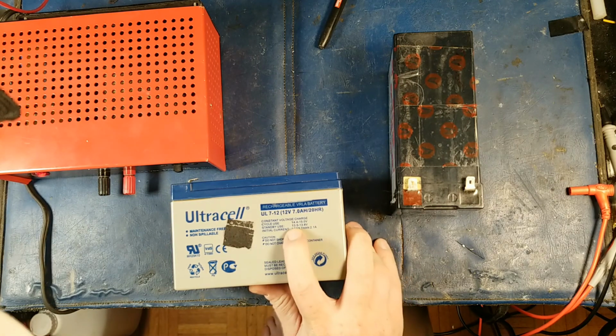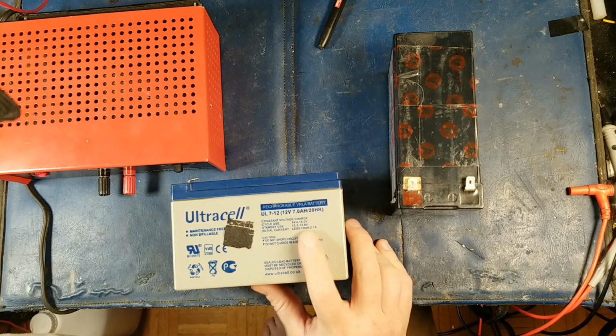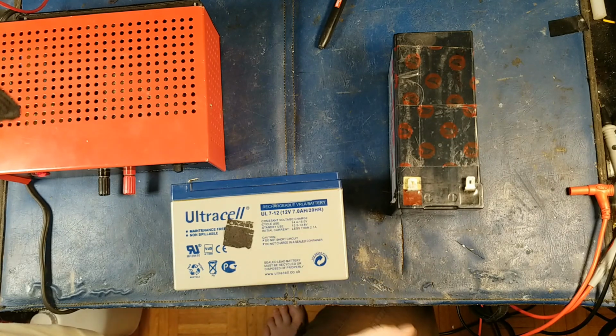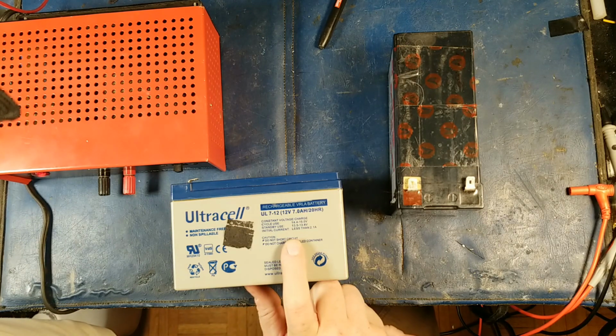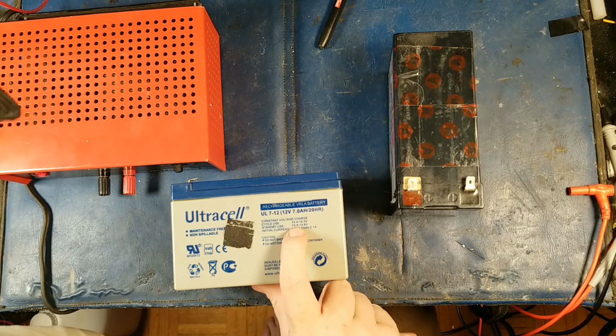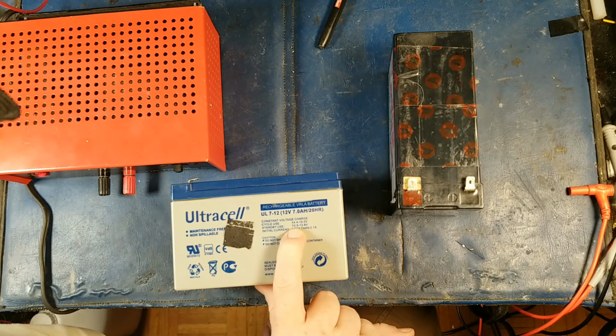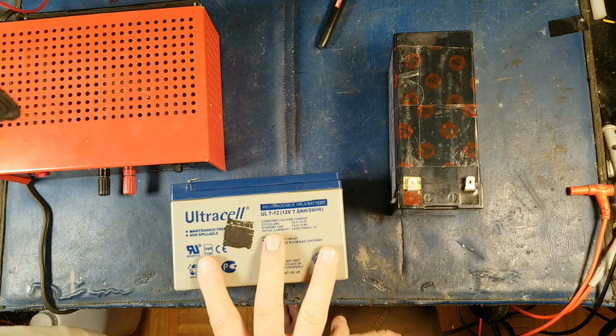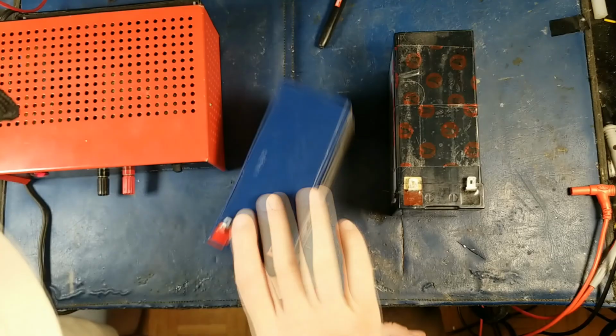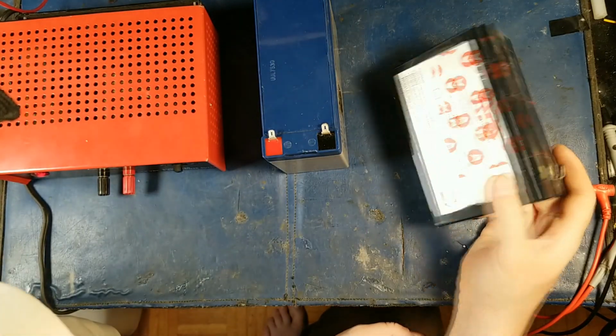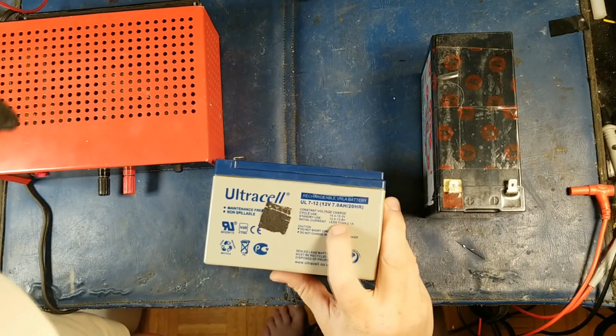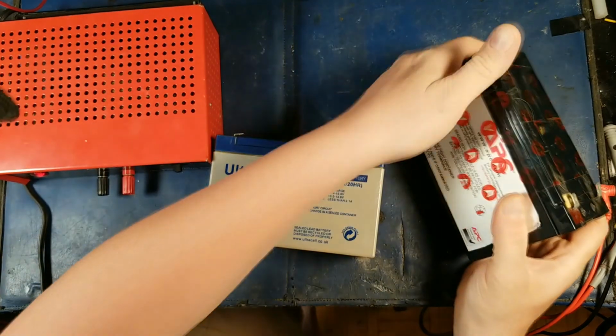Right here you can see 13.5 to 13.8. Personally, I like to stay at the low side of float, because as long as it's over 12.8, while idle the batteries will stay healthy until they're needed. Running them at 13.5, 13.6 on an AGM is perfectly fine — it's a great way to keep your batteries maintained. But if you run them at 14 volts, or higher than 13.8, this happens in a short period of time.